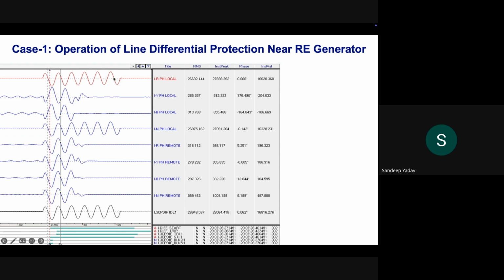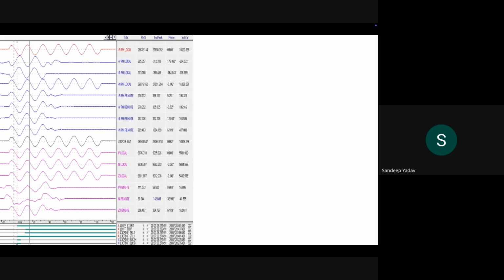Yes, so this is a phase to ground fault in R phase. The fault current contribution from the grid side is 26 kiloamperes. The fault current from the IBR source is close to 300 amps, and it is again zero sequence because it is a phase to ground fault. So the fault contribution from the grid side is 26 kiloamps. The current contribution from the RE generator is only 300 amps, and it is in phase, so zero sequence only.